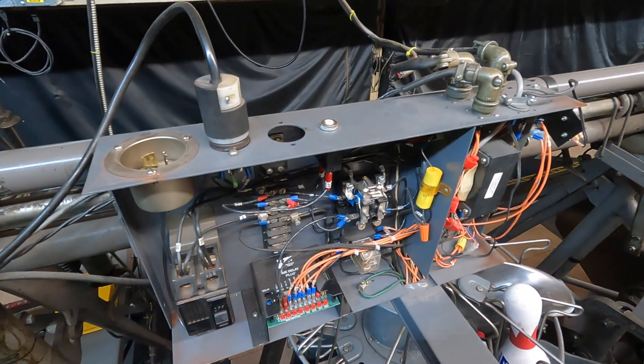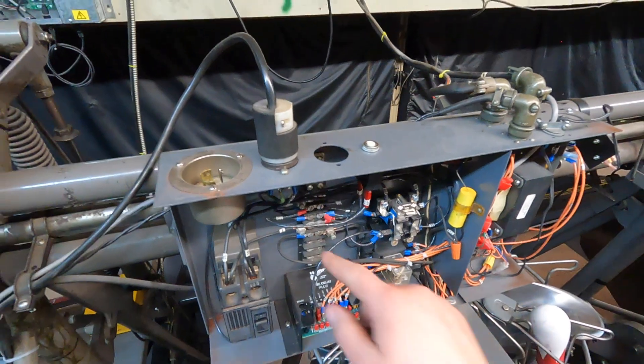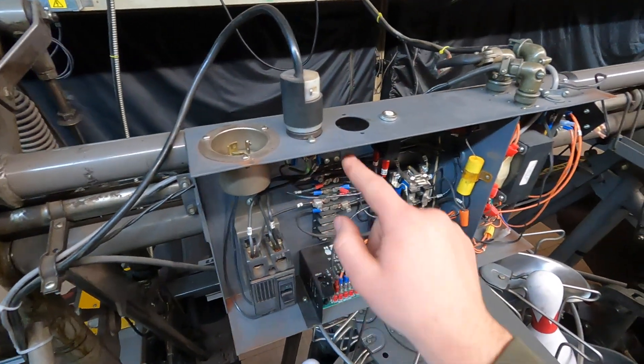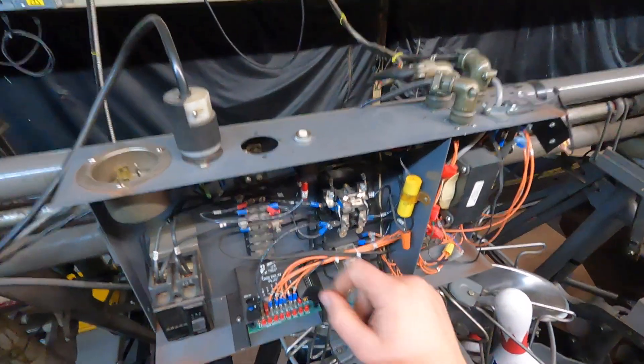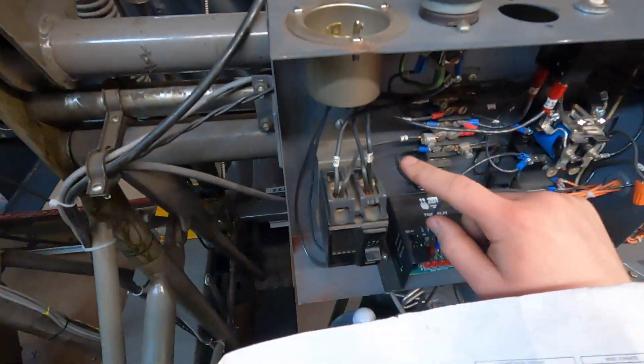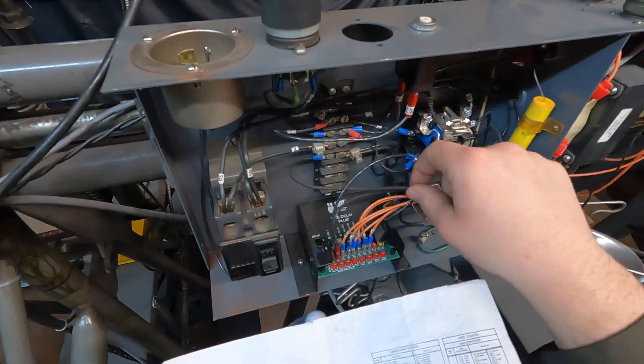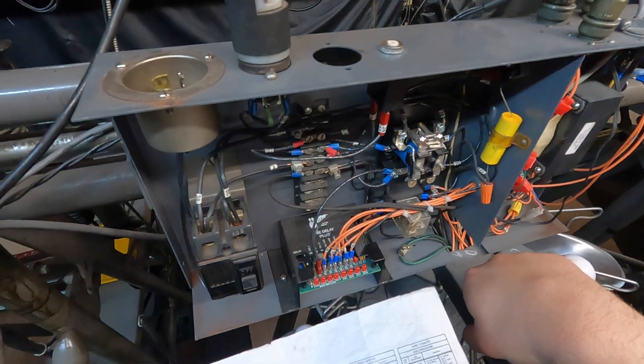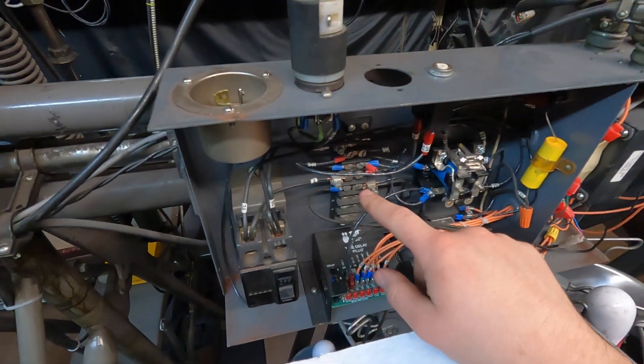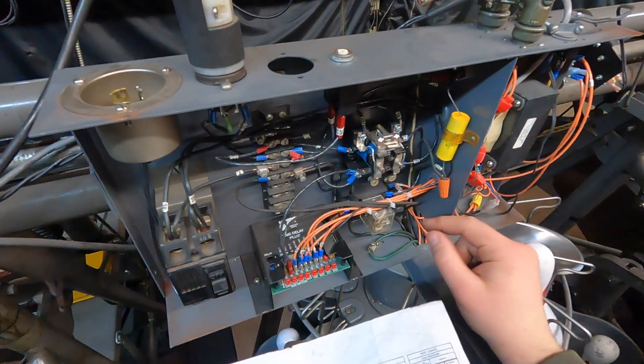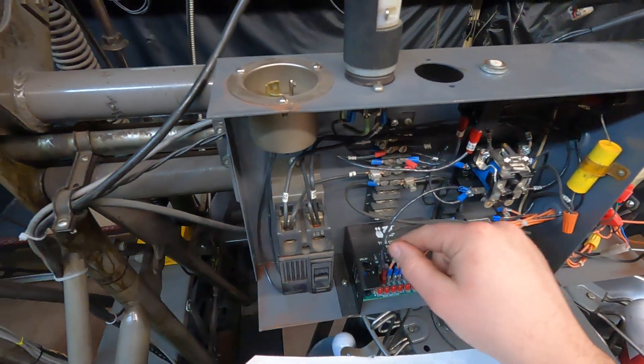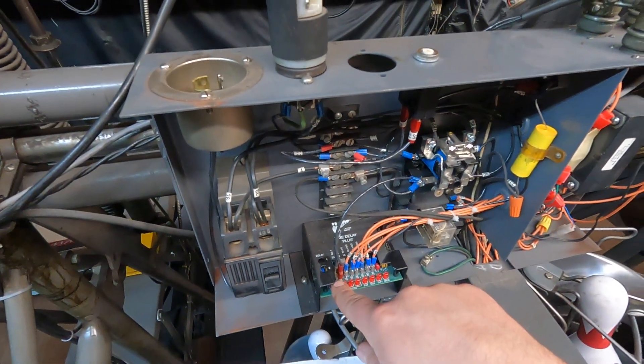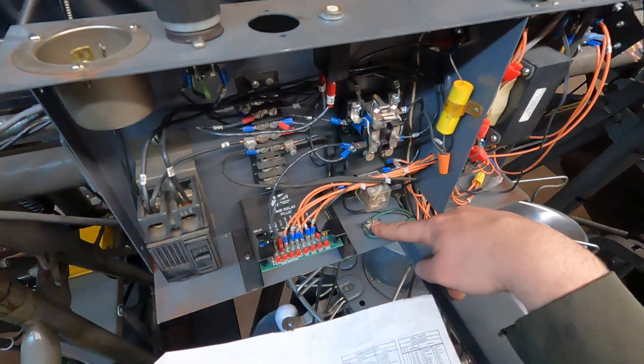And I have never seen anyone else in the United States have them. So normally, yeah, there'd be a wire that goes from here to the pin finder plug up here, but we don't run those. So we don't need it. So they put number 11 over here. So number 11 from the plug should go to D on terminal strip one. Wire 59 from the plug should go to 20 on the time delay and then your ground should go to your ground.